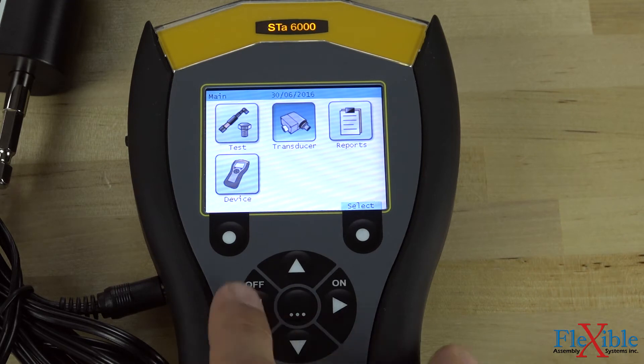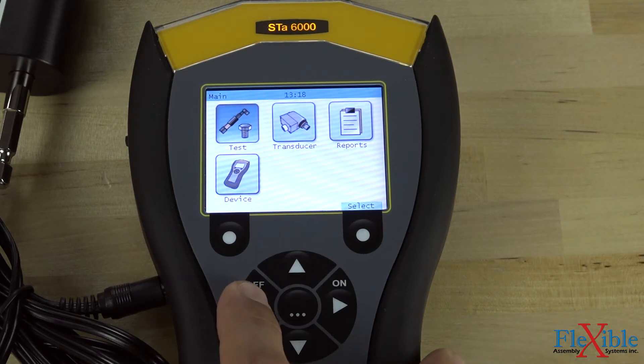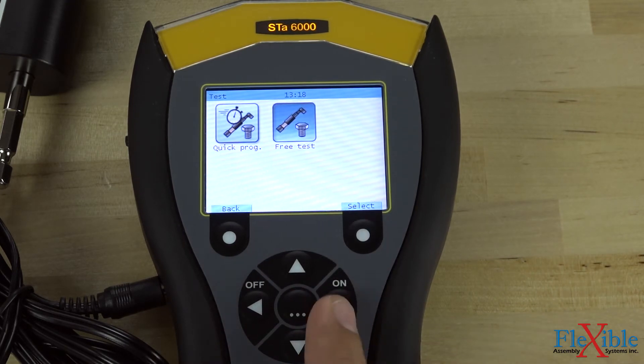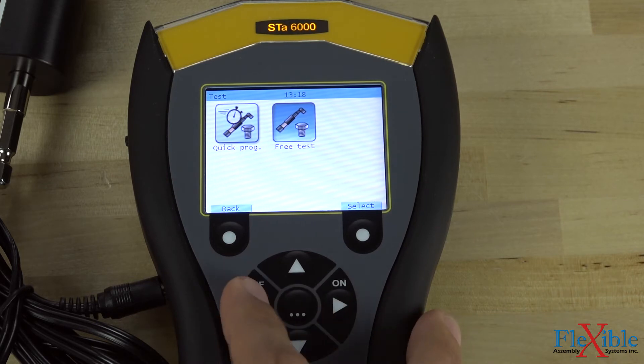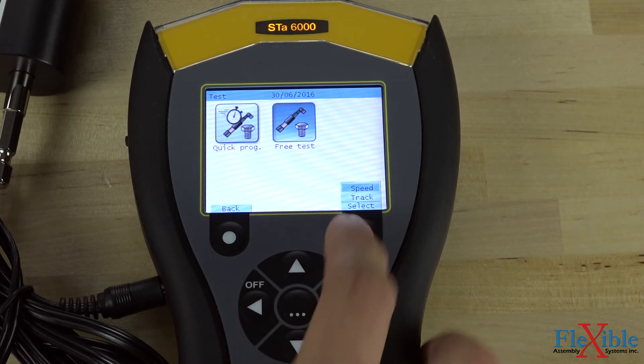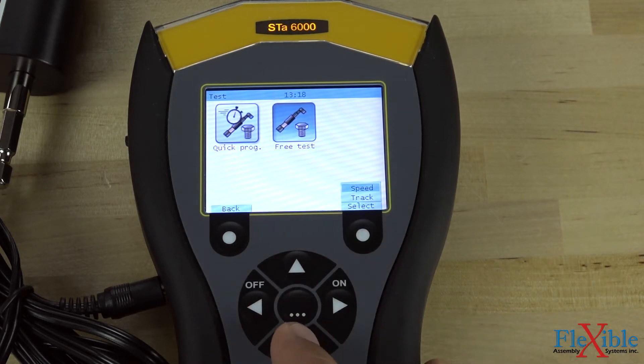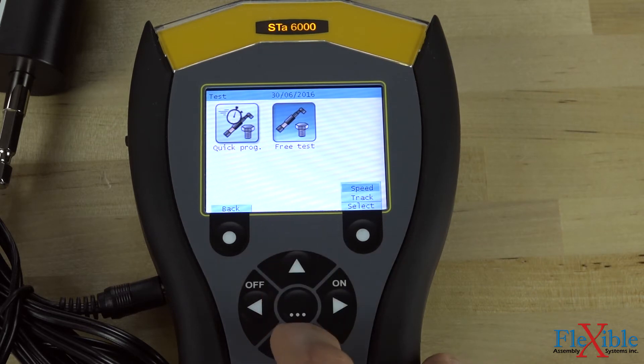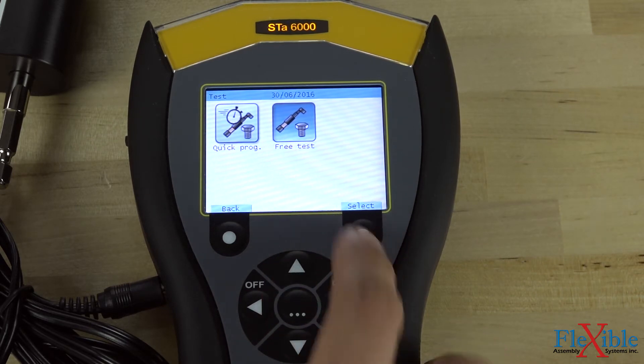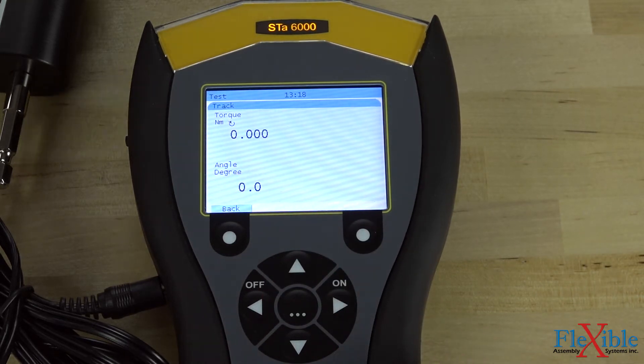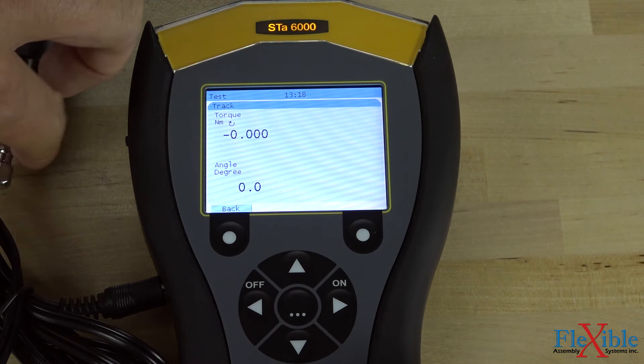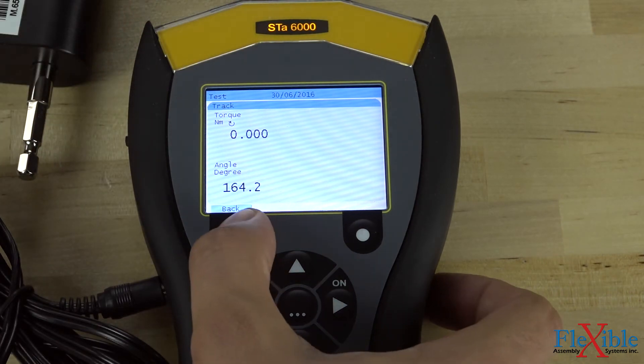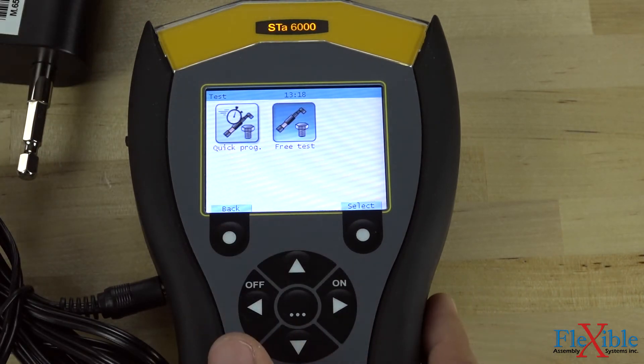Time to set up a test. When you open the test menu, you are given two options: free test and quick program. Free test will give you two options: speed and track. Speed will show you the current RPM and peak RPM of your transducer, while track will display the current torque and angle information. These tests don't save any data, but are great for quick reference.